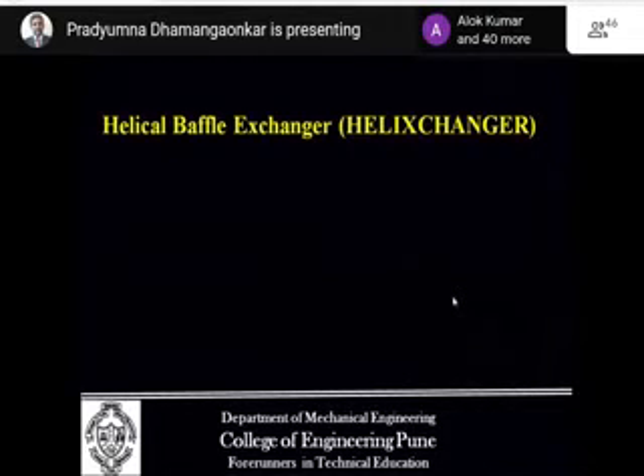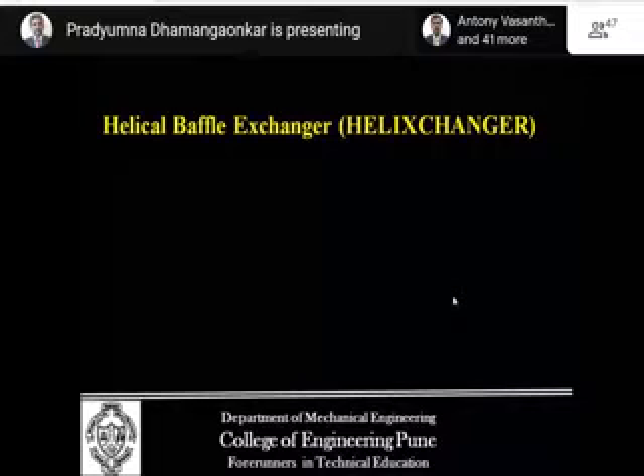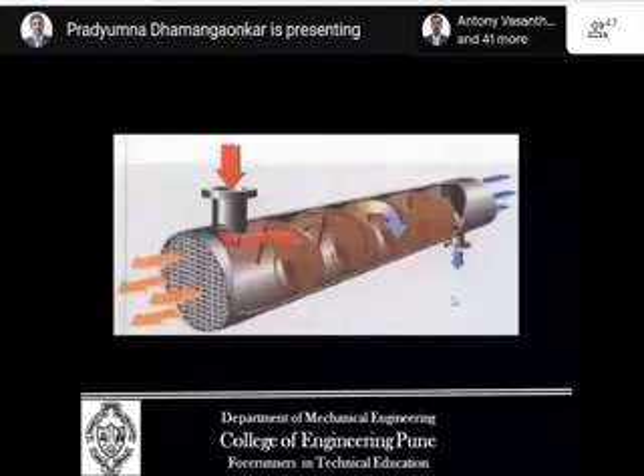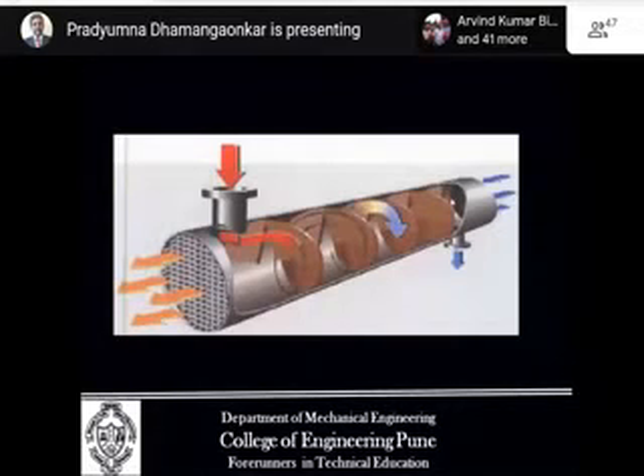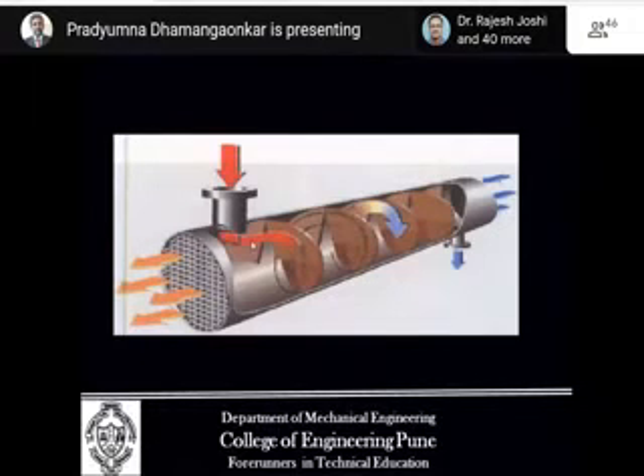Now, these are some of the unique heat exchangers which are called helical baffle heat exchangers or helixchangers. Here, in a conventional shell and tube type heat exchanger, the baffles are vertical, the straight baffles. They can be a 3/4 baffle, half baffle, or half cut baffle. But in this case, the baffles are put in a helical form in different quadrants. They are fixed in such a way that they form a helix. Due to this, there is less resistance offered by the baffles to the flow, and thus the heat transfer coefficient is improved. At the same time, the heat transfer rate is improved.